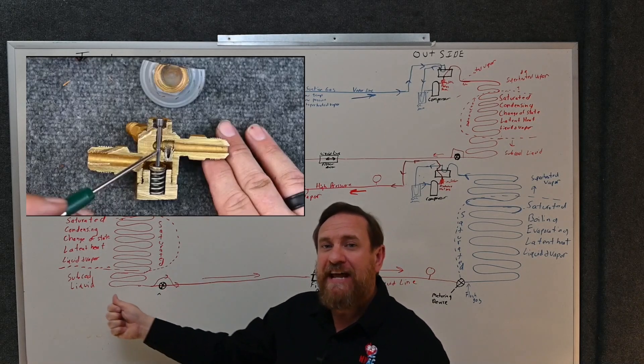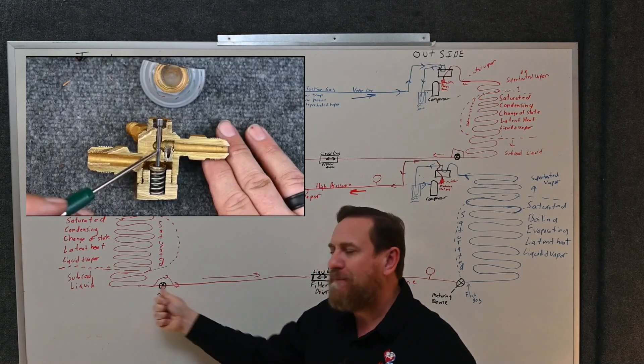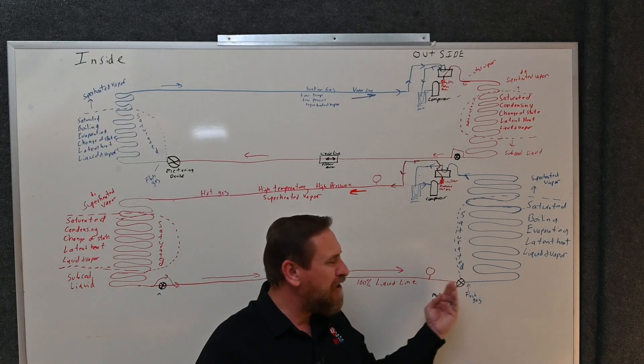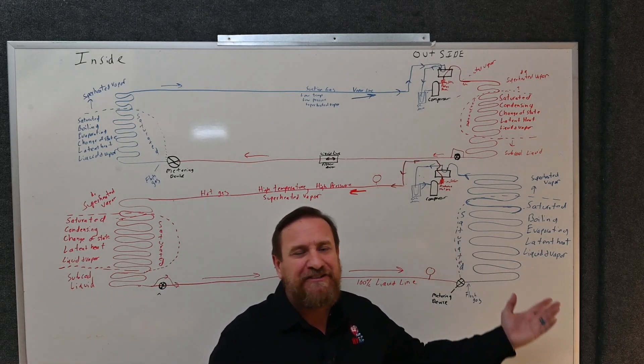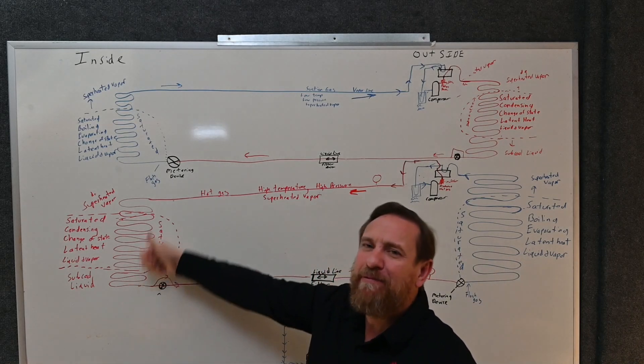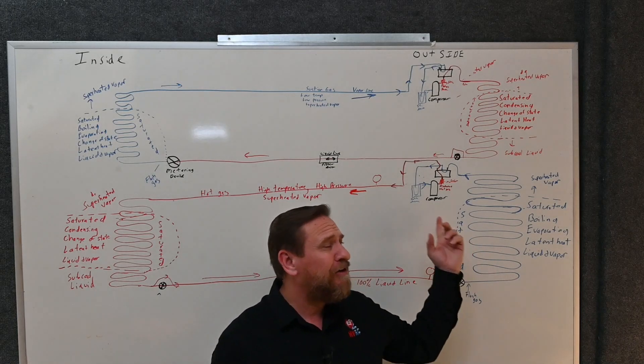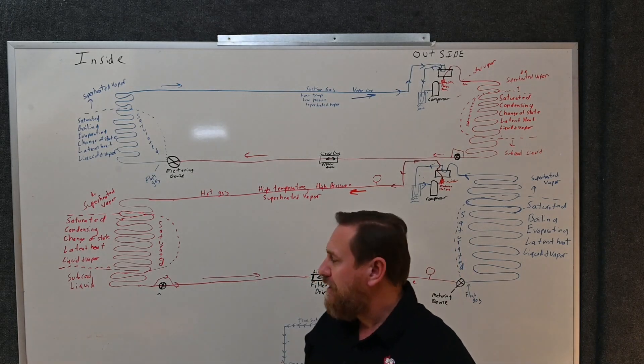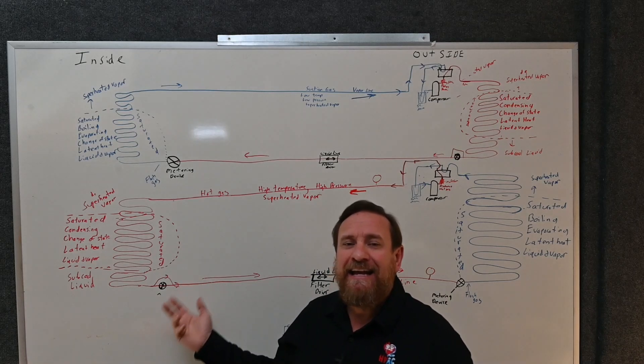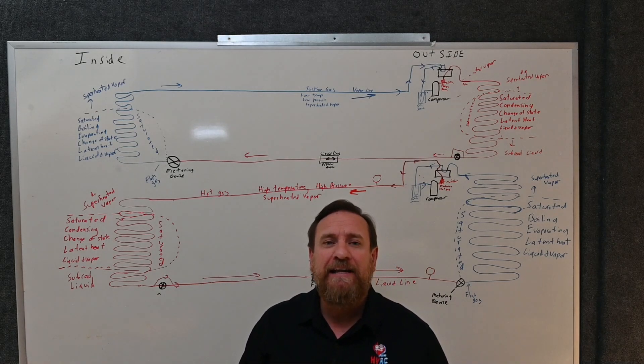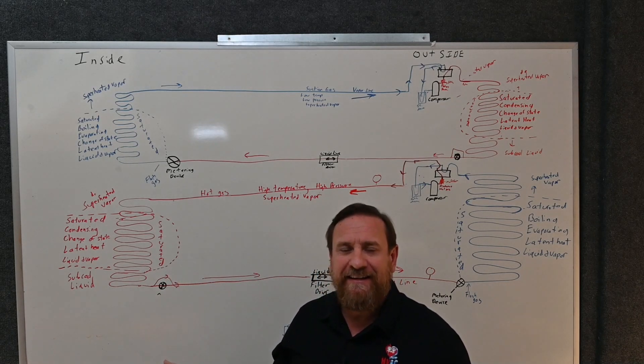Now all of a sudden you have a pressure drop across here, another pressure drop at your outdoor metering device. Your suction pressure tanks and your head pressure spikes. Next thing you know you're tripping on a high pressure switch, and not just high pressure switch, but probably you're going to overheat that compressor pretty quick too. In that case, we want to make sure that we either clean that TXV, take it apart, get it clean, or we're going to replace that TXV.